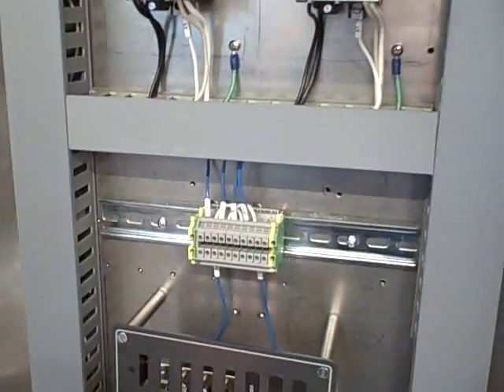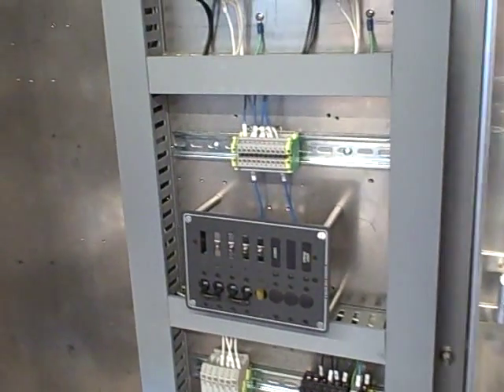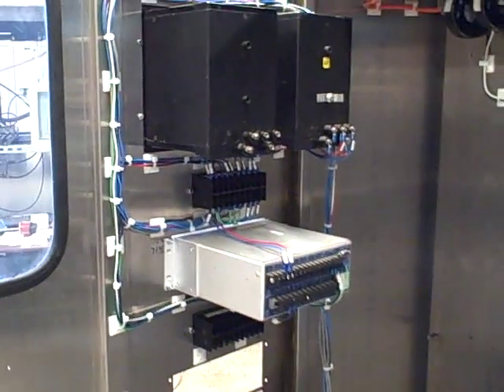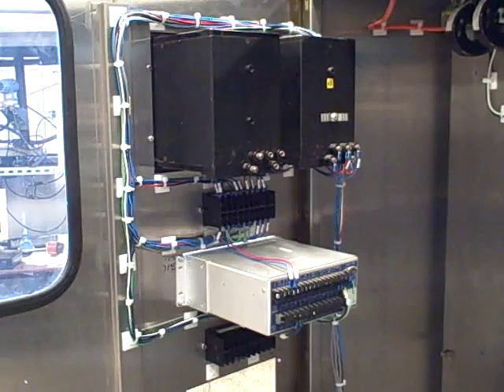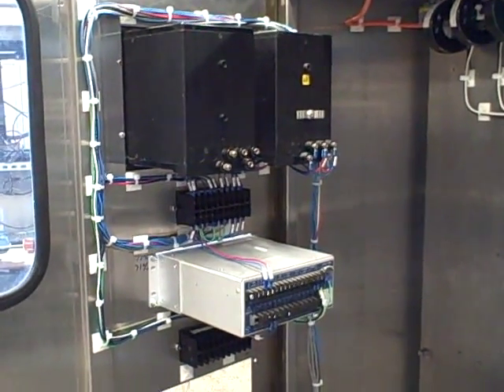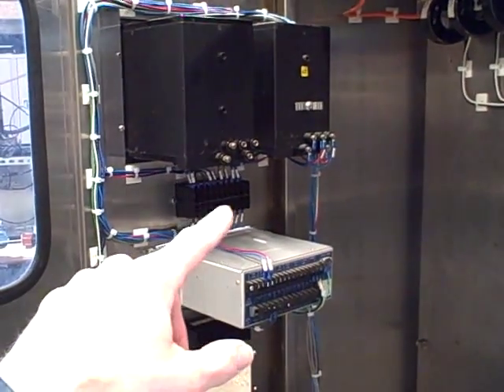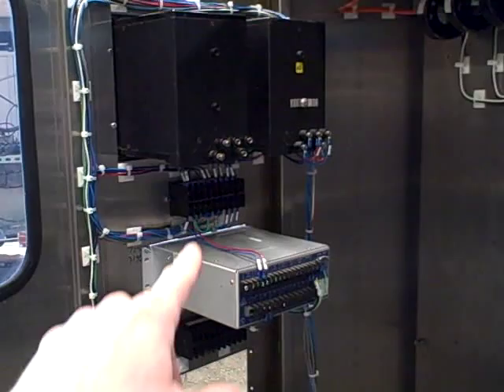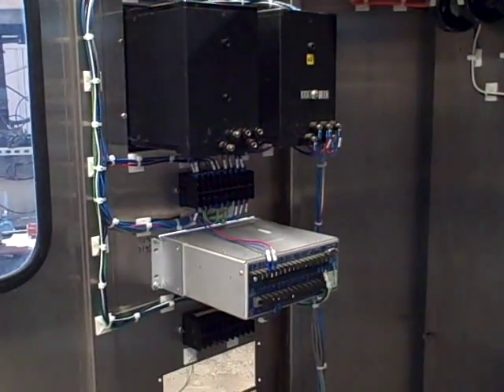The idea is we can demonstrate how these relays work, how we calibrate them, and how we coordinate them. I'm going to make sure later that the electromechanical relays and the digital relays have similar programmed constants so they trip under the same parameters.